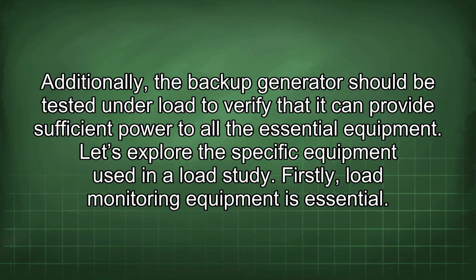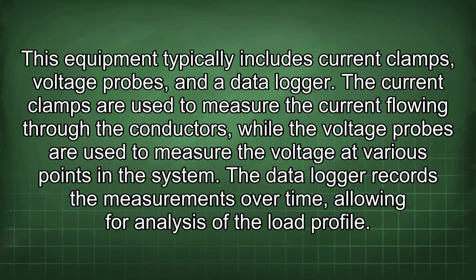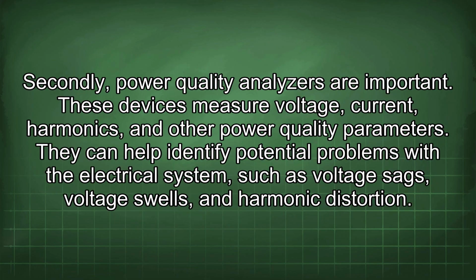Firstly, load monitoring equipment is essential. This equipment typically includes current clamps, voltage probes, and a data logger. The current clamps are used to measure the current flowing through the conductors, while the voltage probes are used to measure the voltage at various points in the system. The data logger records the measurements over time, allowing for analysis of the load profile. Secondly, power quality analyzers are important.